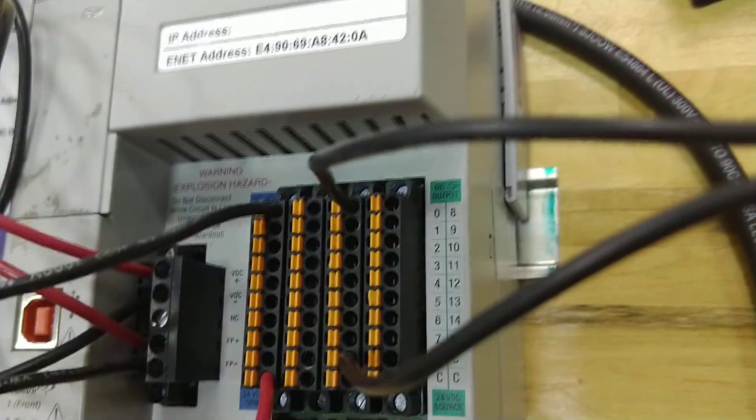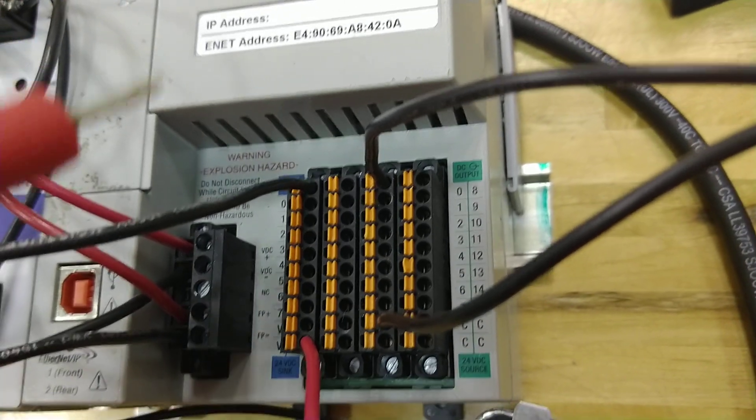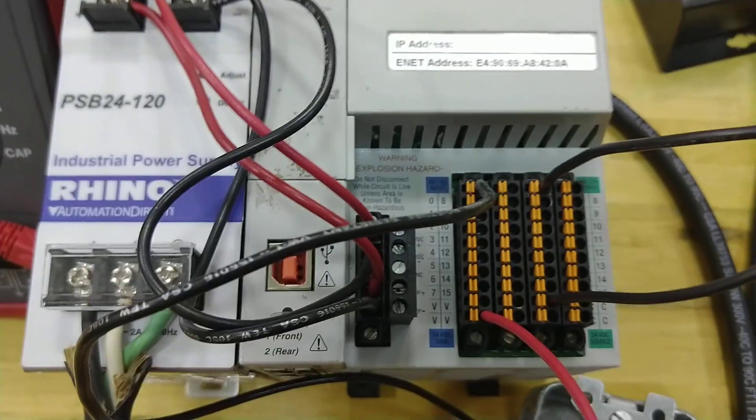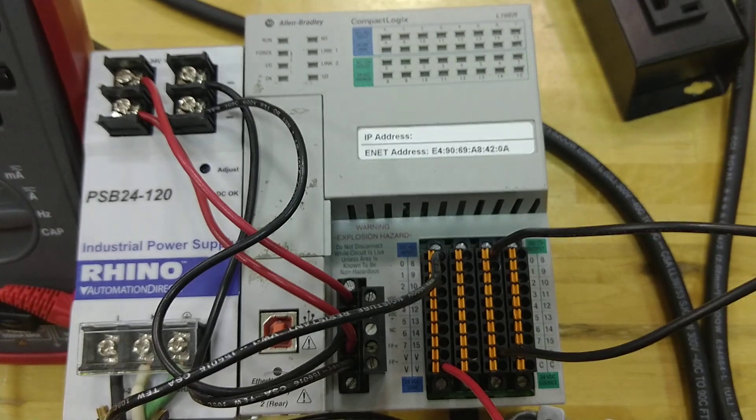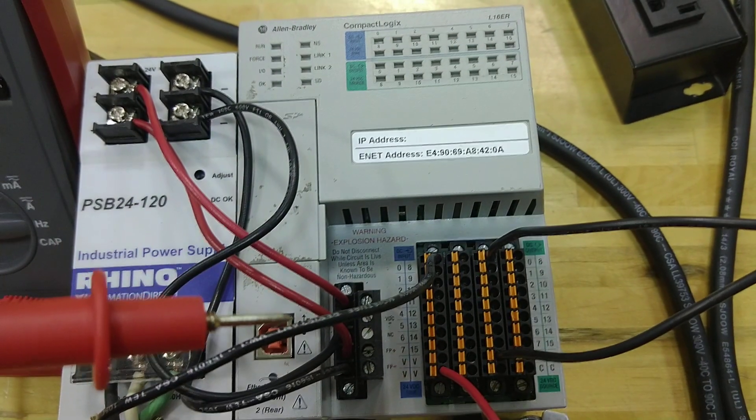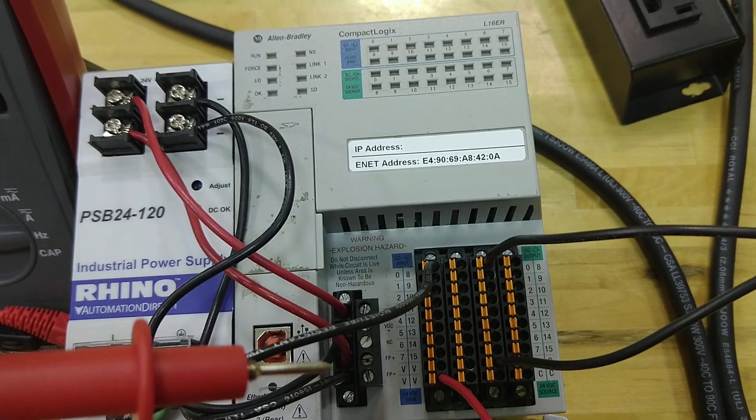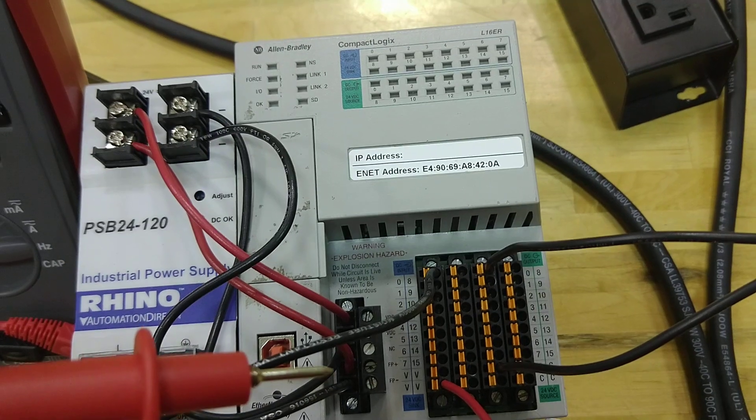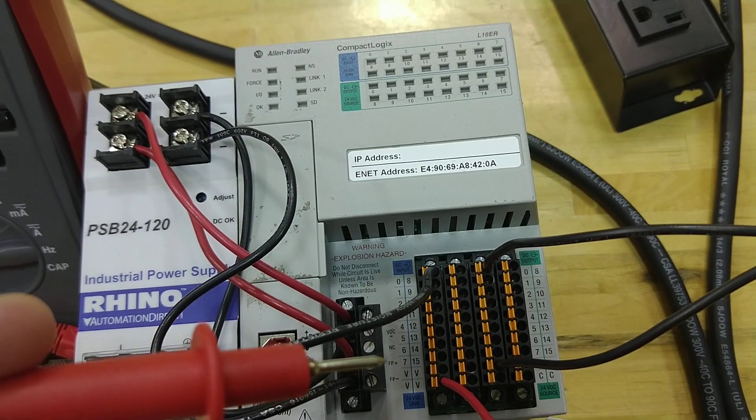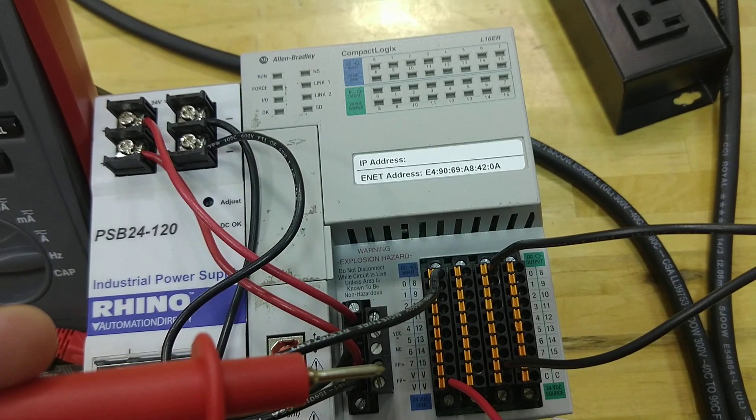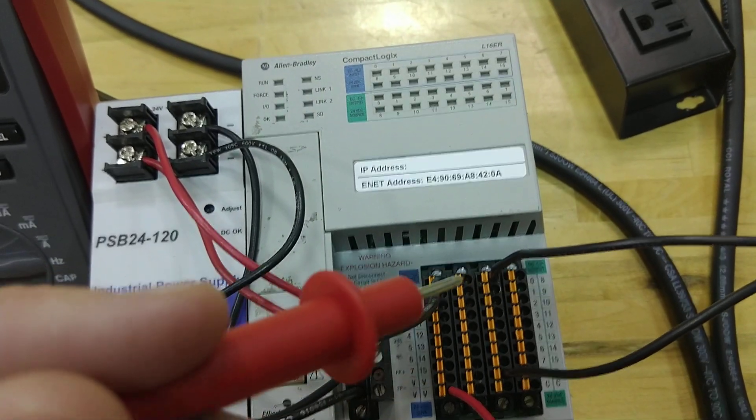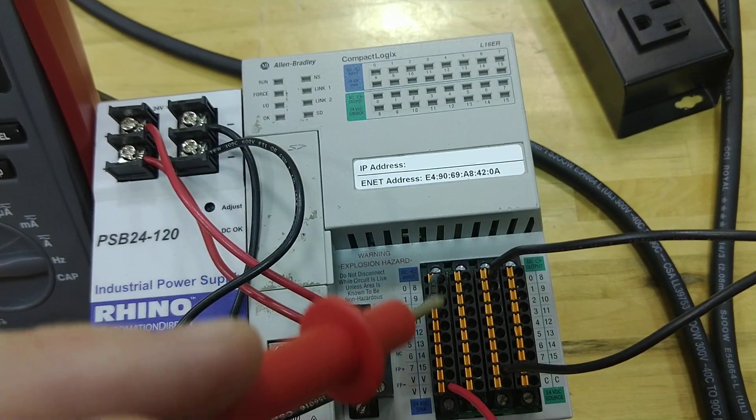If you can see that, get a better look at that. You can see the red, the two reds and the two blacks. That powers the PLC. The top two powers the PLC. And in theory, I could put a control relay or switch before the positive, the field power positive. And that will keep my power from flowing out of my inputs here.